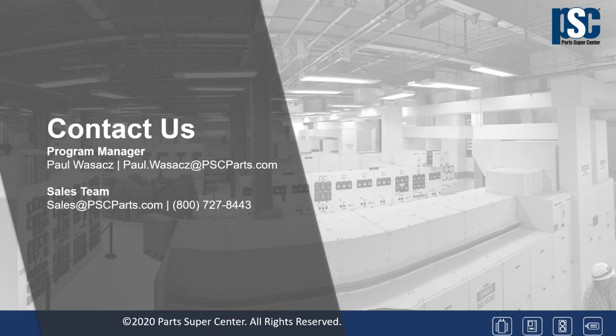And in addition to bringing it up to the latest design standards, we can also modify that equipment or uprate that equipment if the customer so desires. Specific types of uprates would be if you were going to upgrade a circuit breaker from a nominal 250 MVA 5 kV breaker to a 350 MVA nominal 1200 amp 5 kV circuit breaker. So what we would do in that case is we would make sure that the switchgear would match the momentary and close and latch rating of the uprated 350 MVA nominal circuit breaker. That would typically involve bus bracing required to withstand the mechanical short circuit forces at 78 kA, as opposed to the 60 kA momentary forces for the nominal 250 MVA circuit breaker.